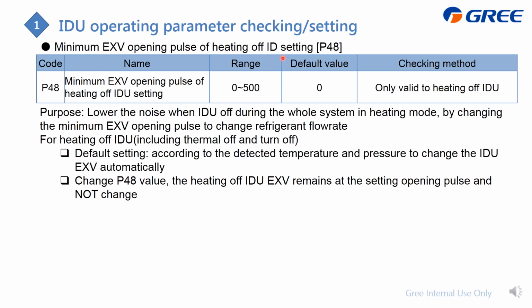For these two kinds of indoor units, even though they are not operating, there is still some refrigerant flowing through. Do you know why? The reason is that the refrigerant from the outdoor unit, from the compressor, is still hot, and this hot gas will release heat at this indoor unit, and then the gas will become liquid. If we make it fully closed, this liquid will accumulate at the heating-off indoor unit, and sooner or later more and more liquid refrigerant will accumulate there, leading to not enough refrigerant flowing in the circulating cycle, which means the system will be short of refrigerant.